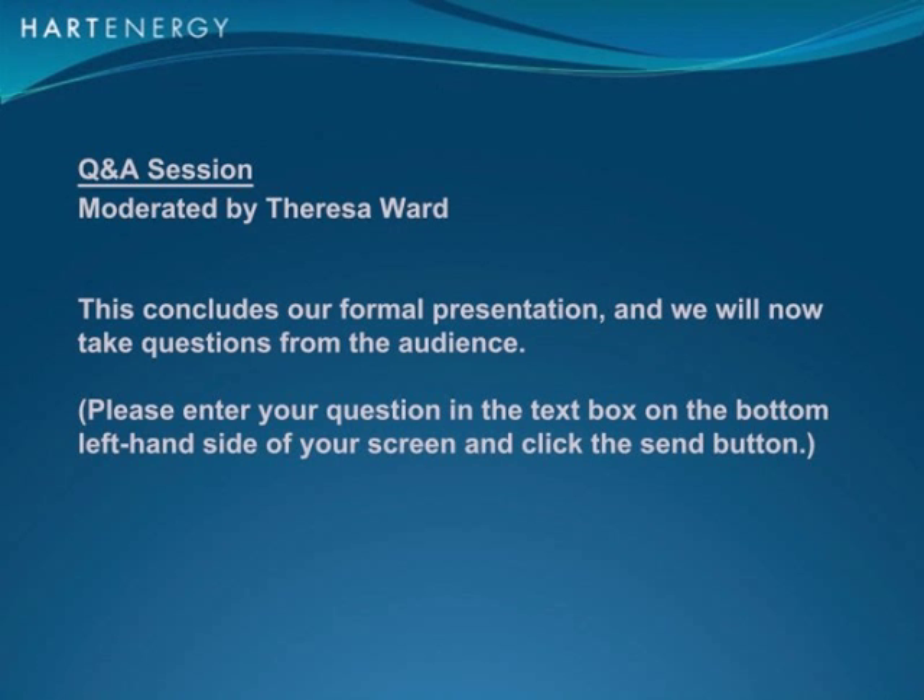Next question: this is part of AMS Suite — what elements are required to set it up on a Honeywell system? Gary: It would run on an application station. It can stand alone from a Honeywell, Yokogawa, or any other control system. It is integrated within Delta V, but we've designed the solution to be available for any refiner with any control system. OPC communication is the way data is moved back and forth — to send an alert to the DCS or to pull information from a historian. The solution runs on an application station in essentially any environment.